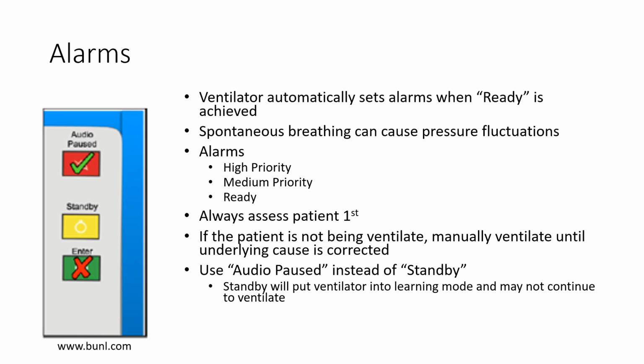When the ventilator enters the ready mode, the alarms are automatically set but can be adjusted by the user. As the patient spontaneously breathes, pressure monitoring fluctuations up to 5 above or below are common. The jet utilizes a red, yellow, green light system for alarms. Green indicates the ready mode. Yellow flashing is a medium priority alarm and indicates alarm limits have been met in the servo or map monitoring. When responding to these alarms, the patient should be assessed first for ventilation to ensure the patient is safe, then for any interventions that may be needed. Then the ventilator and circuit should be assessed.